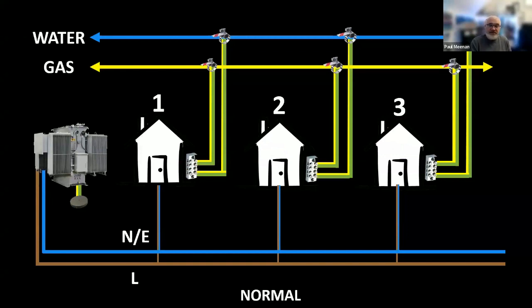So I like to do pictures. So this is a very basic picture of a substation with an earth reference. And in England, what we have is basically a combined neutral and earth in the street now. Because of the age of the networks, that's what they've done. We have a live conductor, a line conductor, sorry, that goes into the house, into a cutout, and then you have an earth terminal where the water and gas will be bonded, or any extraneous services. So that's normal. That's how we wire things, and obviously energy goes in, goes out, back to the transformer, no problem at all. That's how it should work.